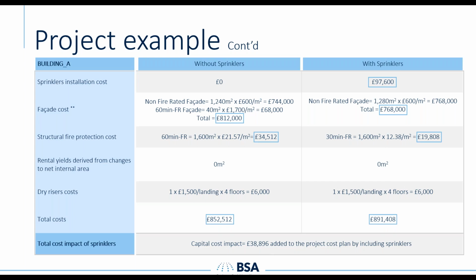What that shows is that, while someone might look at this case as sprinklers not being cost effective for the property, the cost differential isn't as significant as many people would think if you optimize the design with sprinklers. That's the key thing that came out of this work for us - getting people to understand that adding sprinklers has benefits, which can be a monetary advantage in design, and that translates into life safety and property protection too. So you've got to think about the overall picture.